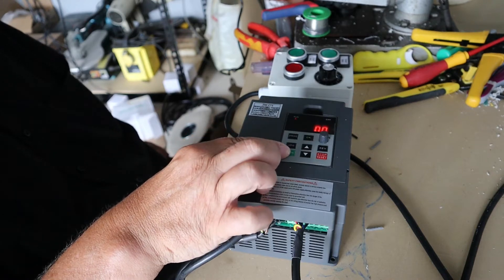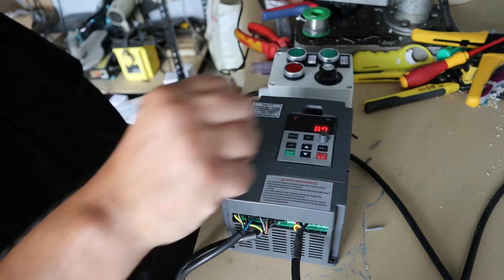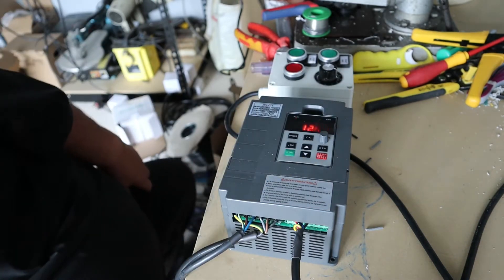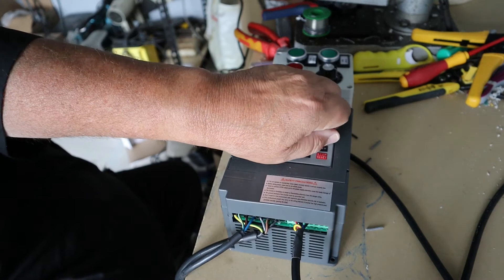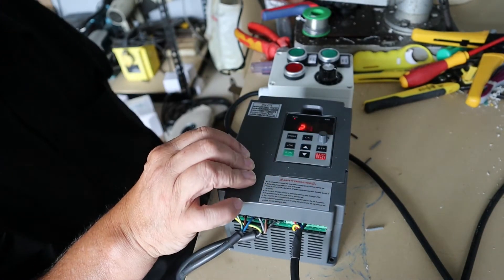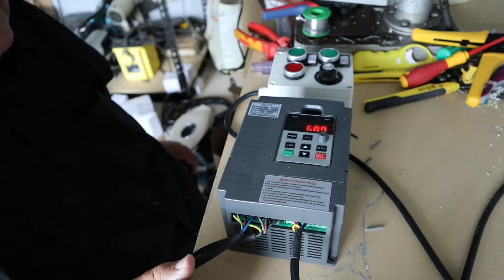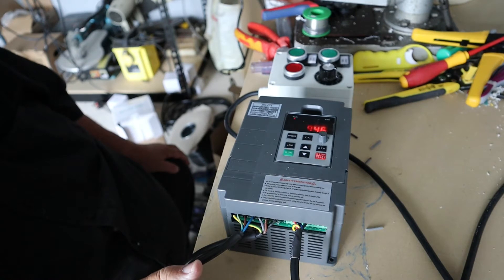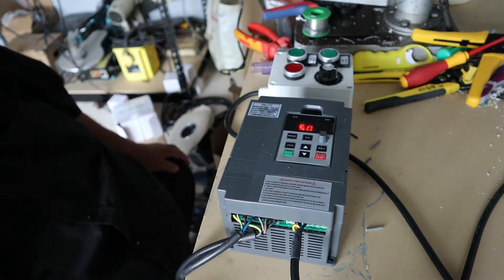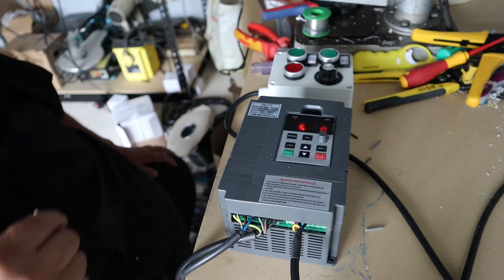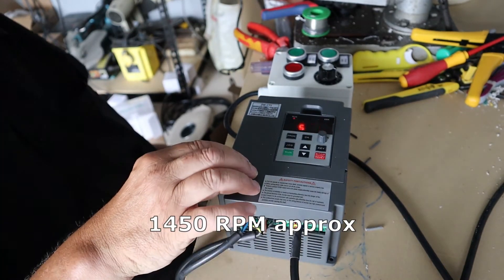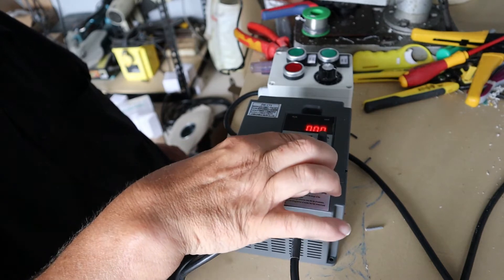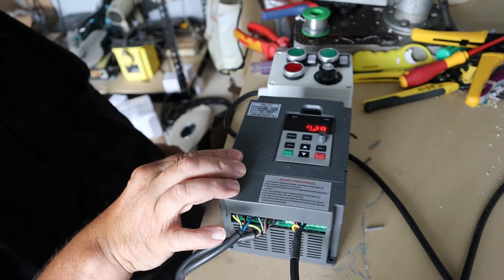Let's see what happens. It is working. It is taking an awful long time to get up to speed. These are set. I think these are preset at about 15 seconds before they hit 50 hertz. So the motor is going to be creeping up to 50 hertz for 1,400 revs. It is taking about 15 seconds. We will stop that.